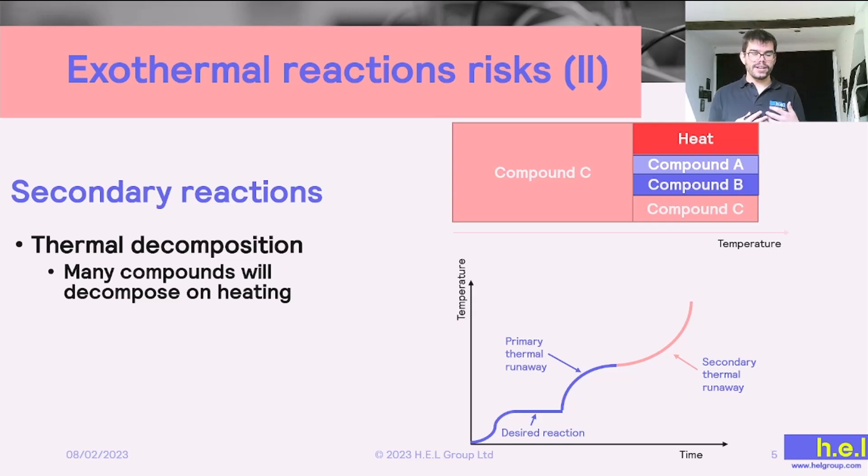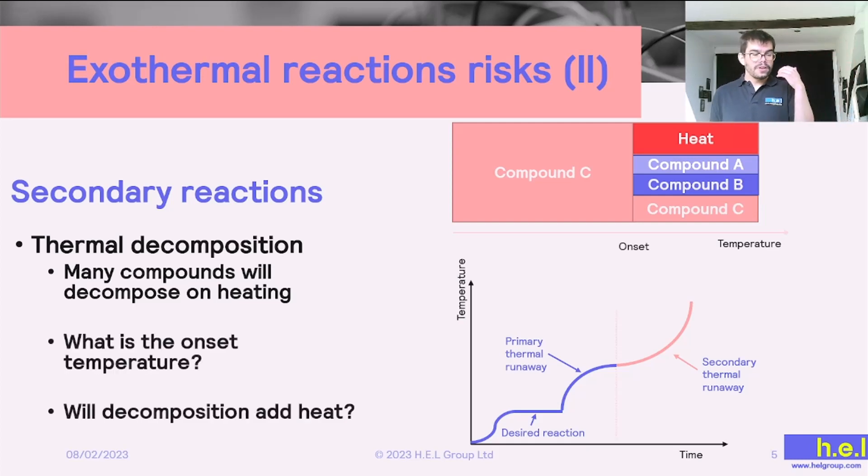So if we study how our reaction would progress, we would see that the temperature increases, then it's going to reach a plateau because of the cooling, but if the cooling fails, then we are going to see a sudden increase again on the temperature. And to predict this, the onset temperature is a very important parameter, and the onset temperature is going to be the temperature at which our decomposition reaction is going to accelerate and we are going to be able to detect it. And also we need to investigate if our decomposition reaction is going to add heat to the system, even worsening our situation.